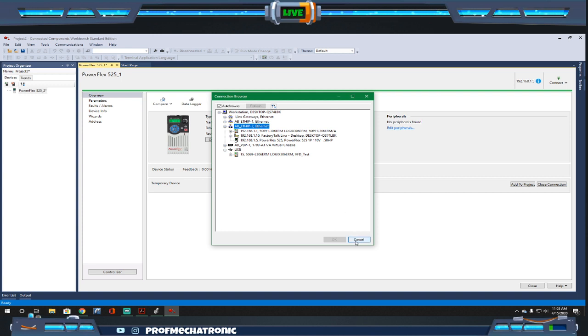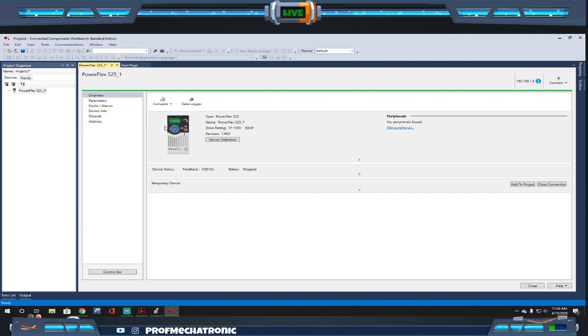As a caveat, the PowerFlex 525 behind the faceplate does have a USB connection, but it's very limited in what it can do. It's basically a USB data tool that lets you put parameters into the drive using just that USB connection on the back. You can't actually create, edit, or do anything on the device itself, and it doesn't power the device - it's only there for uploading or downloading parameters. It's not very user-friendly, so I wouldn't call it a great tool, but it's useful for larger commissioning applications or different setups.